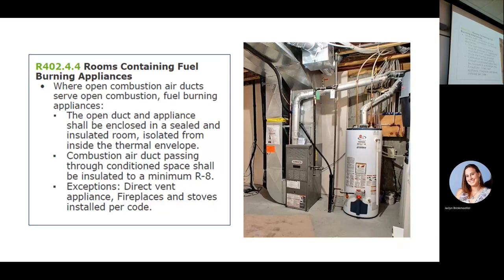So you're thinking, well, why in the hell did you propose something in the code that makes us do so much stuff? Because I'd prefer you use the exception. And what is the exception? Direct vent. 90% efficient, power vented, 2-pipe water heaters, all the problems go away. In the 18 code, it says that if you use all direct vent, space heating and water heating appliances, you do not have to provide makeup air for your kitchen range.